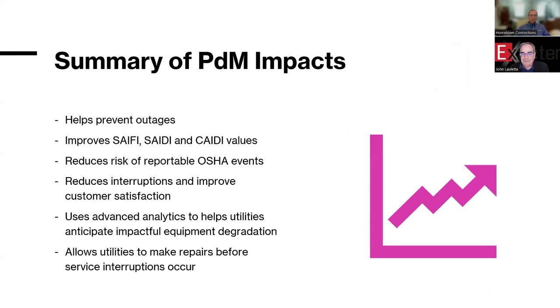So in summary, these are the benefits of the program. It helps prevent outages, particularly unexpected outages. It improves your indices if you measure those: SAIFI, SAIDI, and CAIDI. It reduces the risk of reportable OSHA incidents, which is not only important for that, but for the people who are reported on those events. You don't want your people being hurt at work. It improves customer satisfaction. It uses advanced analytics to make your work impactful to avoid equipment deterioration within your company. And it allows you to replace equipment that's going to fail soon before it fails and avoid the service interruption.